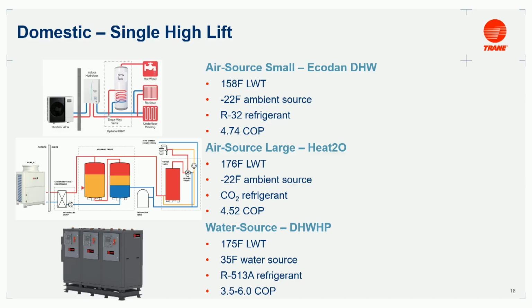Once we get into those larger systems, we use what we call the Heat2O product, which is a larger, more of a commercial offering for apartment buildings, hotels, larger buildings, things of that nature. And this is an air-to-water heat pump, and one of the cool things about this machine in particular is the refrigerant that we use is actually CO2. I believe one of these other guys is going to talk a little bit about CO2, so I won't go into the benefits of that right now. But the reason you're not going to see CO2 in your normal chillers, your normal rooftops, your typical comfort cooling and heating equipment is because it does really well with high lifts. So if you've got an ice rink where you need really cold glycol, or you're trying to do domestic hot water where you need really hot water, CO2 is great for that application. And you're going to see a lot of products in this space that use CO2 or similar refrigerants. And because this is a domestic hot water heater, it never needs to make chilled water. It's always trying to hit that high lift. And so we're using CO2 as a refrigerant.